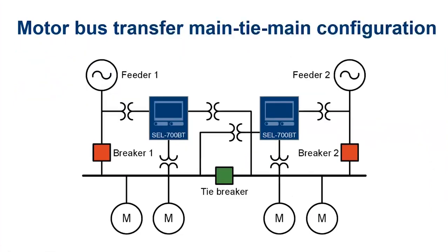We also support a main-tie-main configuration using two 700 BTs connected in this way. So we'll have 3 voltages here, 3 voltages on the other side of the tie breaker, and 1 voltage on the bus. And then similarly for the other 700 BT. And there is no communication required between the two bus transfer relays.